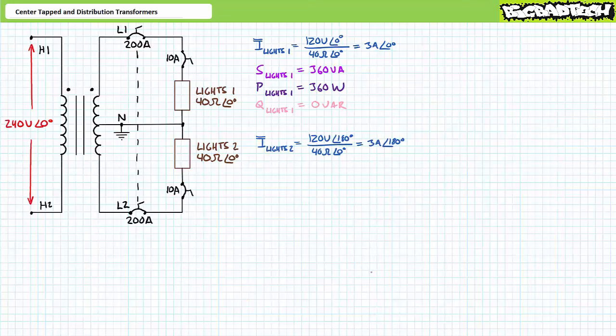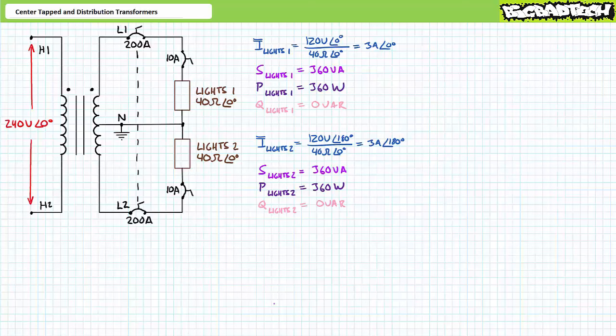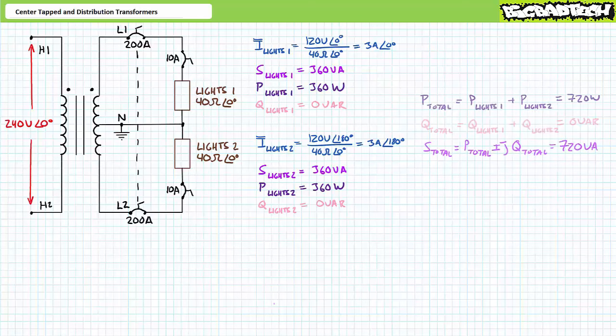Similarly, an application of Ohm's law demonstrates the second lighting load draws 3 amps at an angle of 180 degrees — equal in magnitude yet perfectly out of phase with the lighting load on L1. A subsequent application of the AC power formula demonstrates the second lighting load also consumes 360 volt amperes of apparent power, of which 360 watts is directed towards real power and zero vars towards a reactive interchange. In totality, this system is supplying 360 plus 360, or 720 volt amperes.